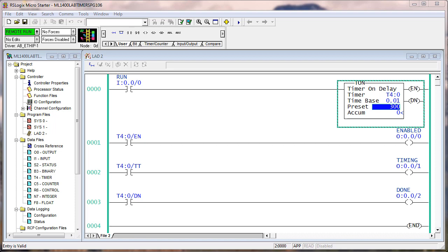In the manual you had to fill in some blanks next to some actions based on the timer and put them in the order in which they occurred. Rung goes true — then the timer timing bit is set and the enable bit is set. So: rung goes true, enable bit is set, timer timing bit is set, accumulate increments, and when the accumulate equals the preset, the done bit is set and the timer timing bit is cleared. When the rung goes false: enable bit is clear, done bit is clear, and accumulate is clear.